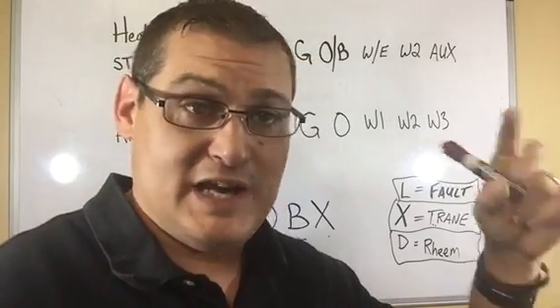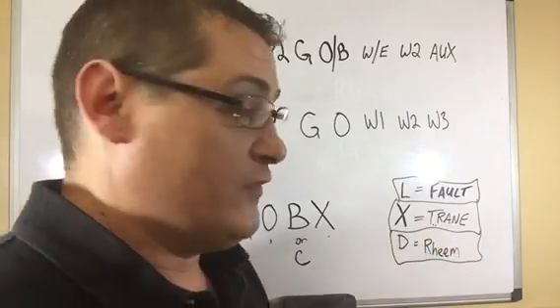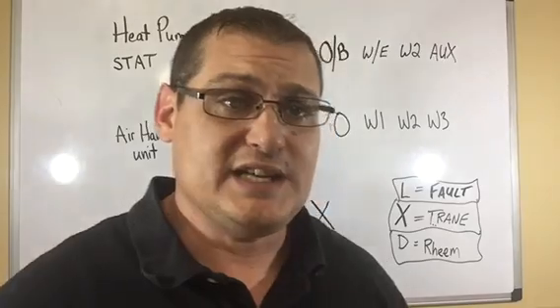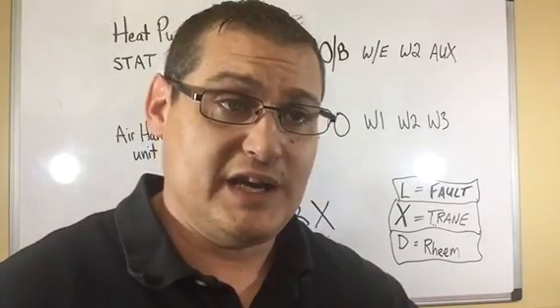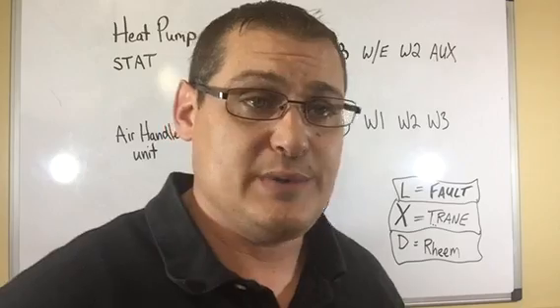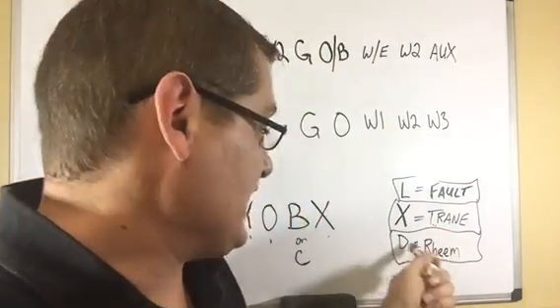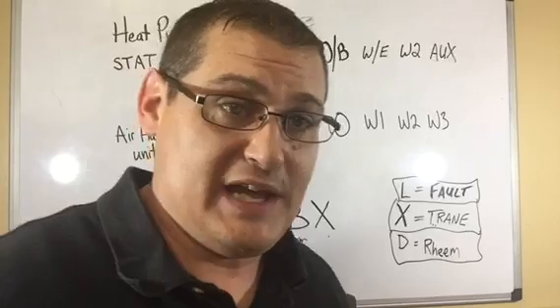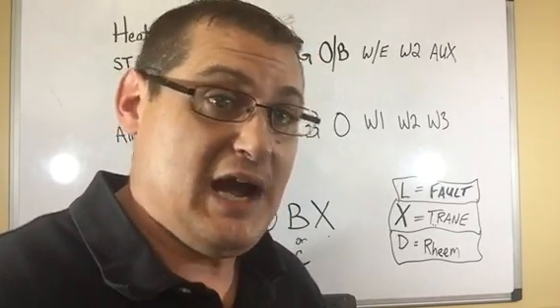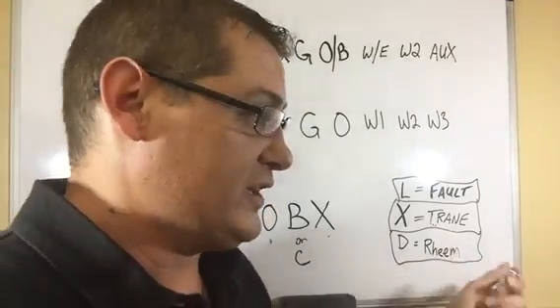Then we have the X terminal for Trane. Trane uses X anytime the unit goes into defrost. We need the backup heat running, so it sends a signal into the air handler to turn on the strip heat. That's what X does. In Rheem, they call it D, and it does the same thing. When it goes into defrost, it sends power to the backup heat to power while the units in defrost. It doesn't matter what they call it. They could call it Q for all we care, as long as we know what it does.